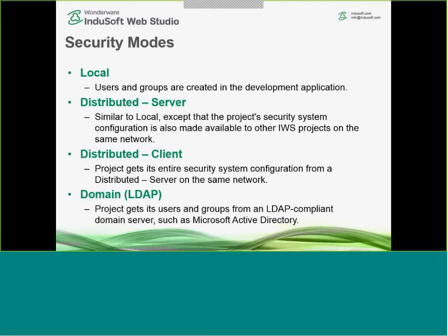The other option is using what we call domain security. So if you do have an existing Windows domain, or some other directory service inside your company, or if you want to create one, then you can configure your LDAP compliant domain service, create users and groups inside that service, and then tell InduSoft to connect to that service for authenticating users and getting their group memberships.